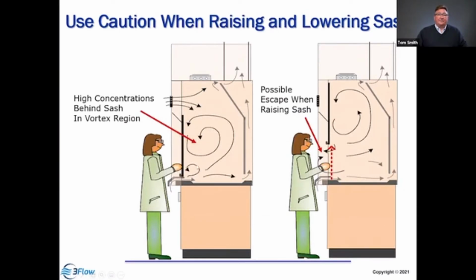We also want to look at the movement of the sash. When the sash is in the closed position, we get flow through the airfoil and through the bypass into the hood, and this vortex forms to accumulate materials inside that hood. When you open that sash, that high concentration can escape out and expose the occupant and then be recaptured. So that response time and the aerodynamics inside the hood are very important to minimize that potential for escape. And that's why we say open the sash slowly to allow for this system to recover and capture materials, and that's why we're going to test it in what's called the sash movement effect test.